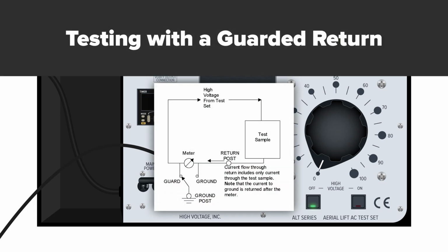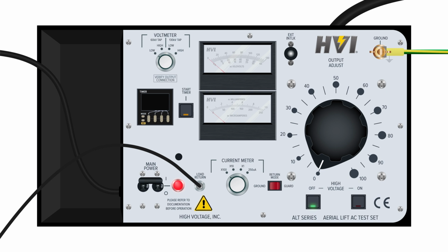Testing with a guarded return. For certain tests, you may want to measure withstand capabilities by measuring only the current that flows through the return lead, and not any of the current going through the ground lead. The use of the guarded return feature allows for very accurate current measurements in such cases.